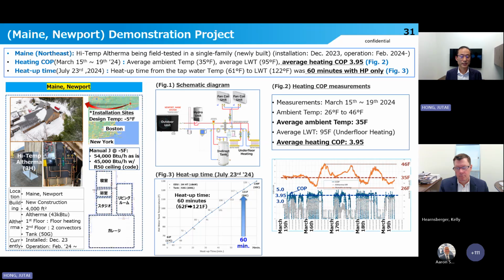Their building is around 4,000 square feet, -5 degree design temperature, and the heating load is 45,000 BTU. They installed underfloor heating on the first floor and 2 convectors on the second floor for heating and cooling operation.